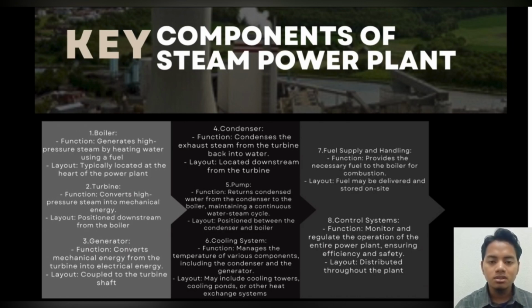Number 4, condenser. The function of the condenser is to condense the exhaust steam from the turbine back into water. The layout is located downstream from the turbine. The condenser uses cooling water from a nearby source such as a river or cooling tower to reduce the temperature of the steam, turning it into water.